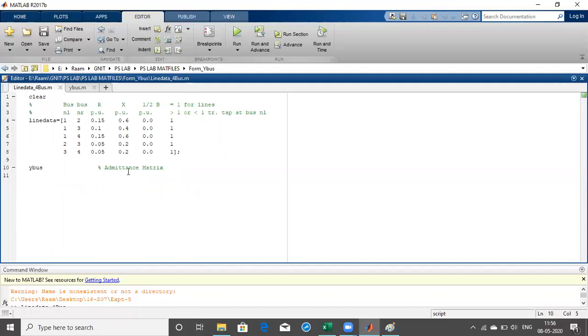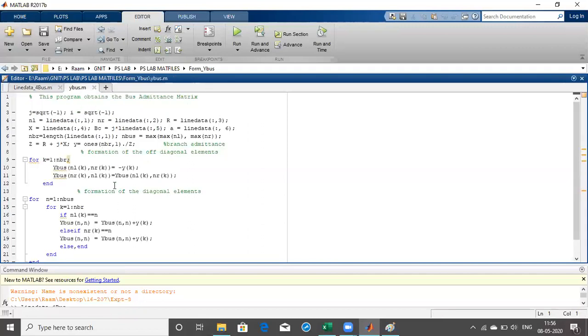ZET = R + j*X, since the given data is in terms of impedance. We then convert impedance to admittance: Y = 1/ZET. This calculates the admittance for every branch, so Y(k) gives the admittance of the k-th transmission line. This completes the branch admittance data needed to form the Ybus.